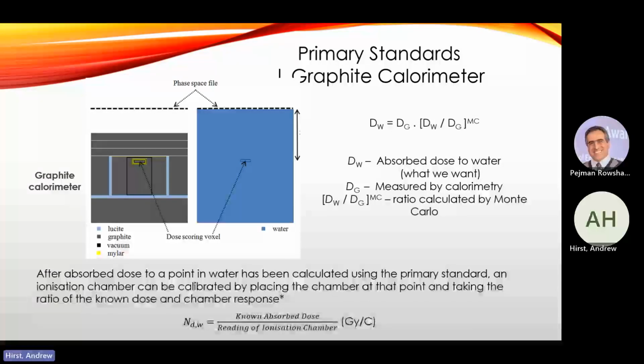Anyway, so you can get the calibration coefficient by placing your chamber there and measuring that response. You know your dose, you've got your charge from however much is read off the electrometer, and this is your calibration from the primary standard. So that known absorbed dose divided by the reading of the chamber, and this is in grays per coulomb. Usually on the certificate, they'll give it in, I think, milligrays per nanocoulomb, all the same stuff.